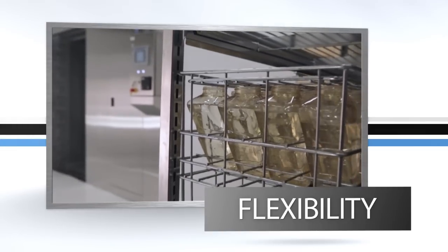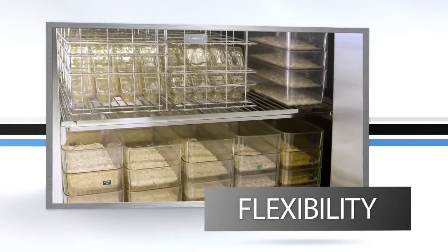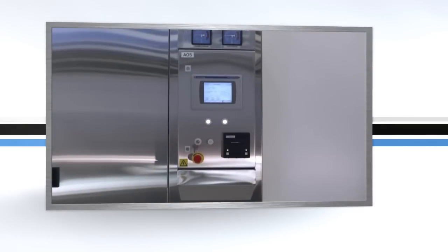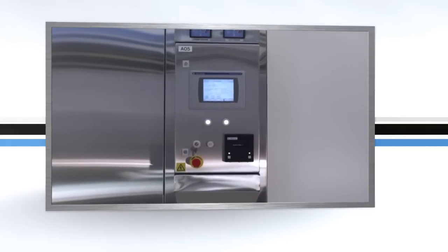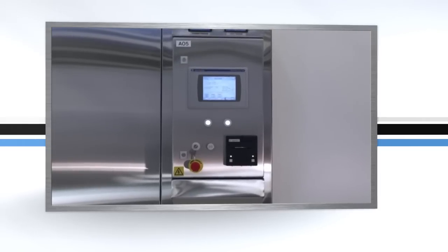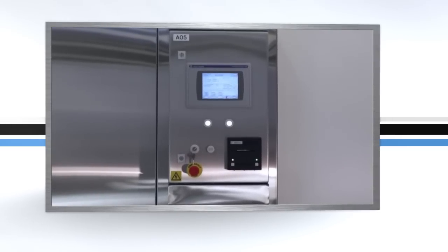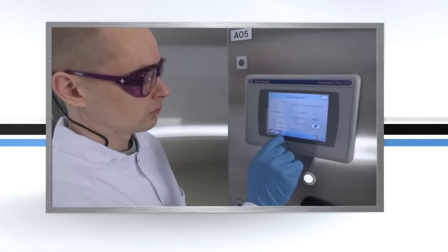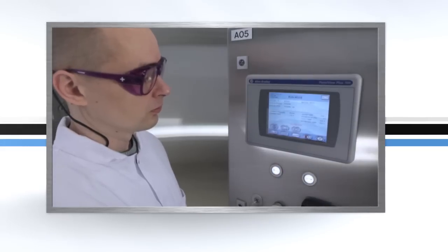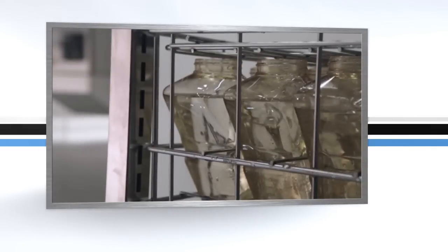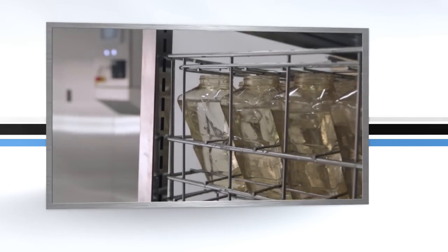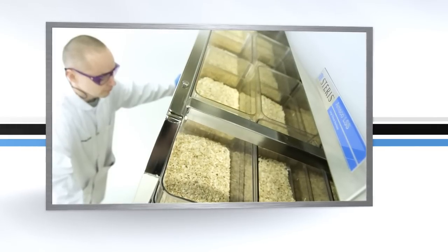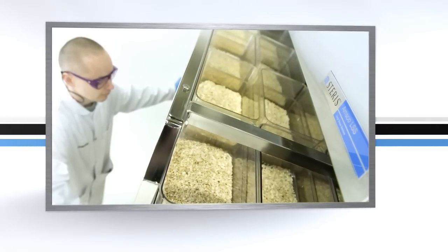The diversity of applications in a typical laboratory animal research facility requires flexible sterilization processes. The user-friendly Allen Bradley PLC control helps you easily operate the system to adjust and monitor critical system parameters. The control allows the user to program up to 20 cycles, providing the flexibility to configure cycles specific to your load requirements. The cycles available on the AMSCO LSS ensure that you can effectively process hard goods, porous goods, and liquids in both vented and non-vented rigid containers.